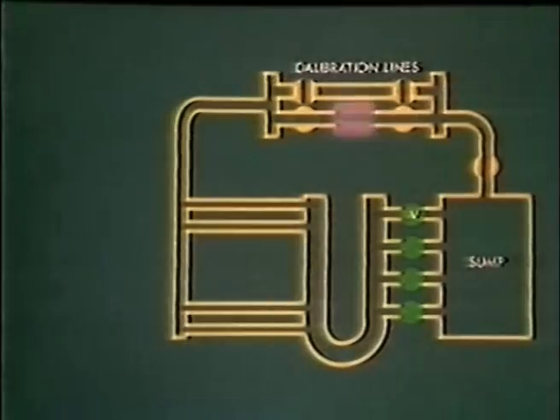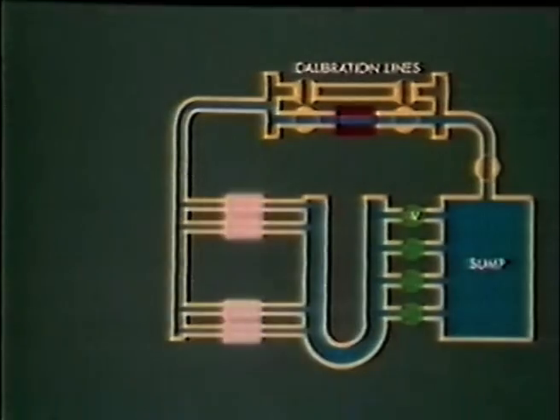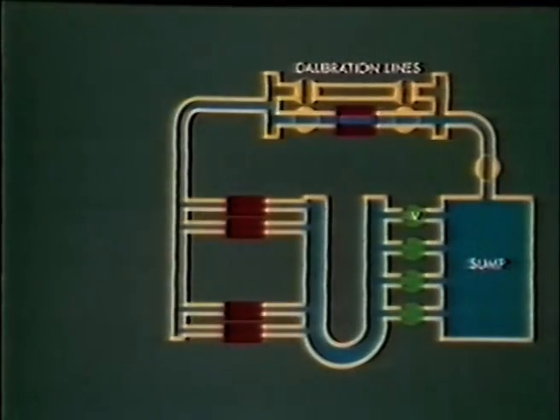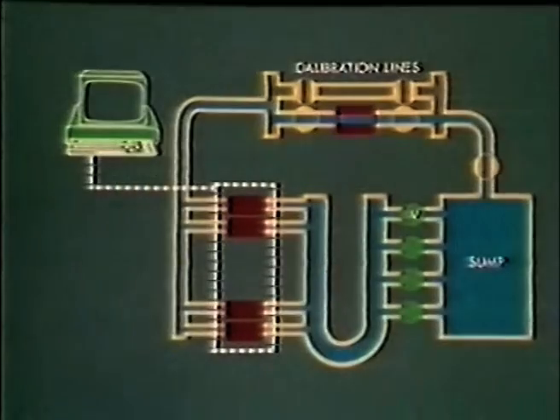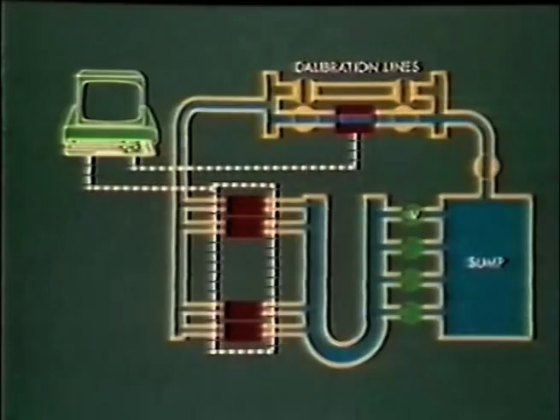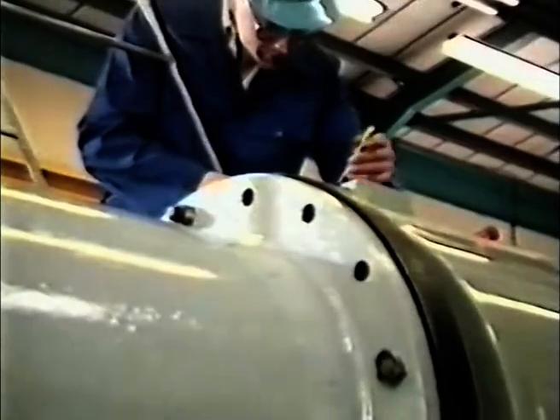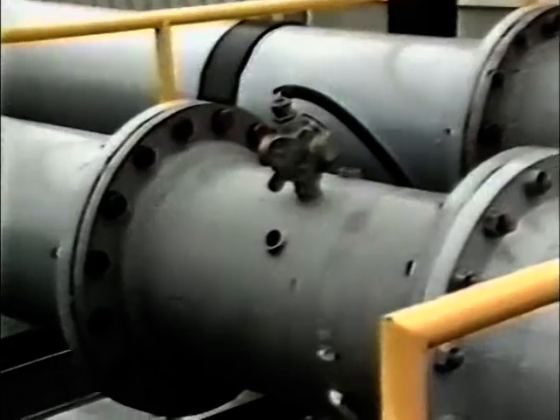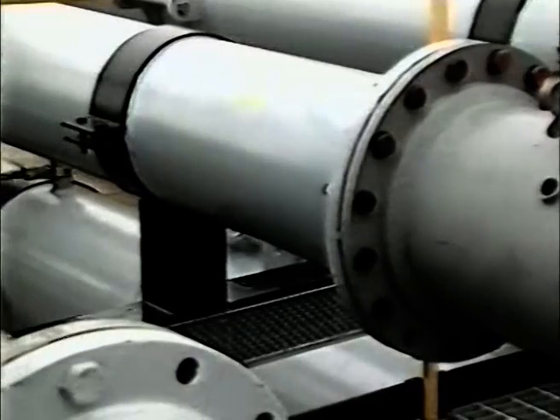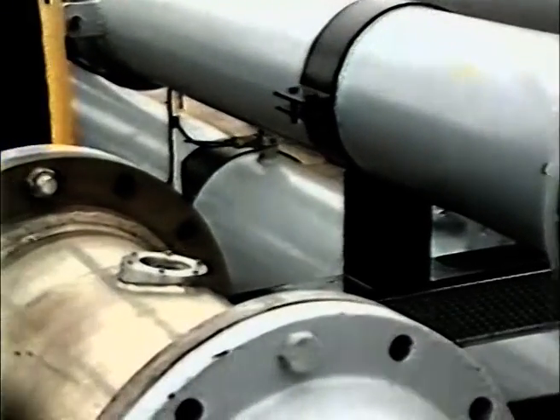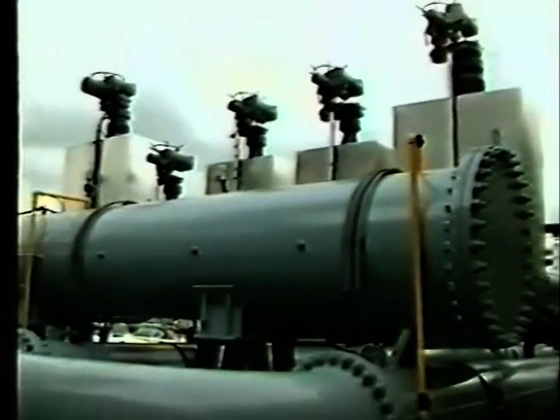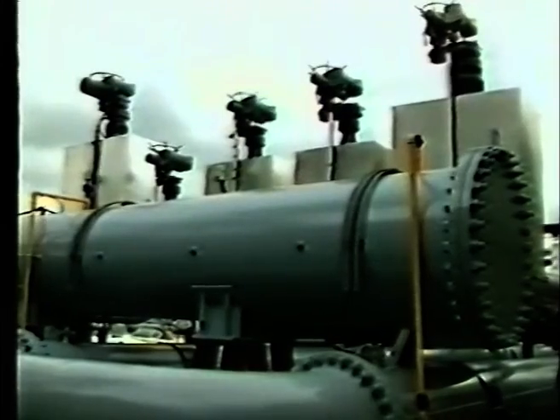The basic principle is that the meter under test is in the same flow loop as up to 4 highly accurate reference standard meters. The output from these reference meters is read by the computer and compared against the readings from the meter under test. There's the meter being tested. The reference standard meters are located outside. These valves allow water to flow down any of these lines.